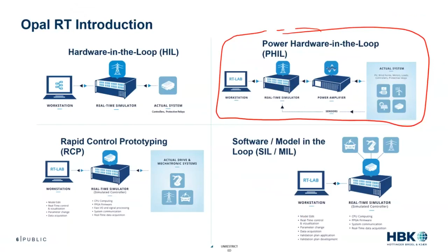So a little bit more about what power hardware in the loop is. This is a more detailed diagram, but it's when we control a real power source using set points from a real-time simulator. These set points come from an environmental model, and the power flows to an actual device, whether that is a controller, an inverter, a wind turbine, or a solar panel. It flows to and from. Usually we're talking about 4-quadrant amplifiers that can absorb and generate current.